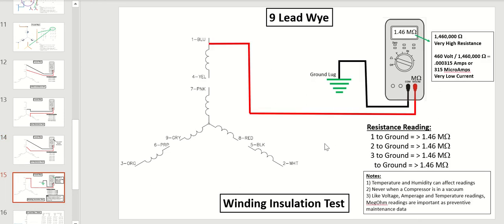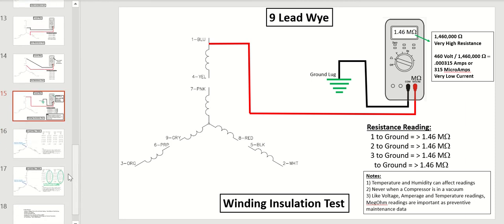The megohm test, again, we're just testing for resistance to ground. We want to make sure we have a very, very high resistance. We don't want any internal current leakage in the motor, which would indicate damage to the windings.